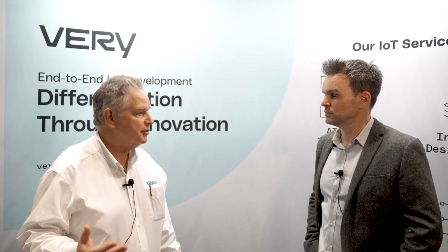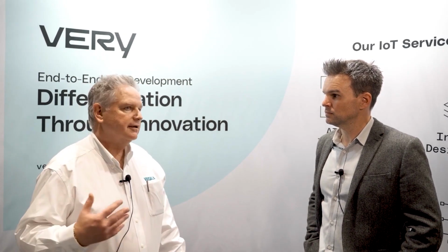We've been getting a lot of inquiries lately about indoor air quality. Energy savings has been really big. One of the other sensor technologies we developed measures CO2, and it's used for demand control ventilation, where you can use the CO2 levels to indicate when a building is populated and when it isn't, and optimize your HVAC system really based on true occupancy. The CO2, which measures the breath you exhale, can indicate the volume of people when they're there, and you can adjust accordingly. The idea has been around for decades, but traditionally these sensors have been incredibly unreliable - they'd have to be calibrated at 3-month intervals, which is impractical. We've developed our own unique sensor called CARBOCAP that takes that 3-month calibration interval and extends it to 5 years, so it becomes very practical to put in the field. It's accurate, stable, and reliable.